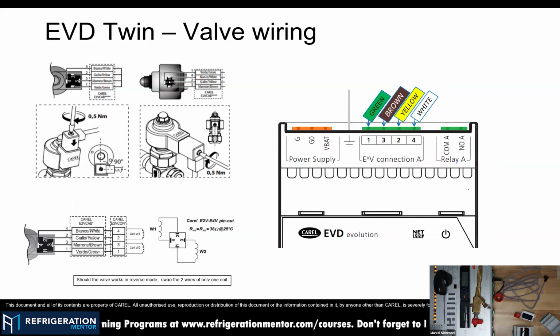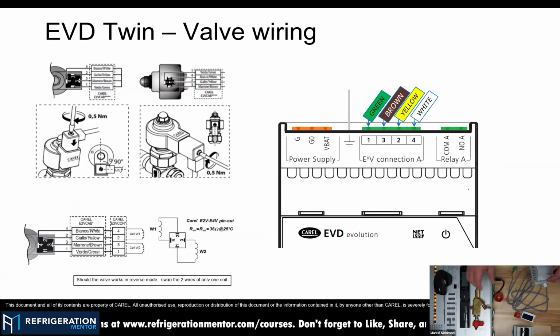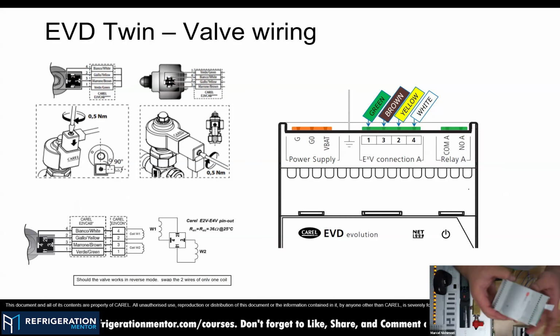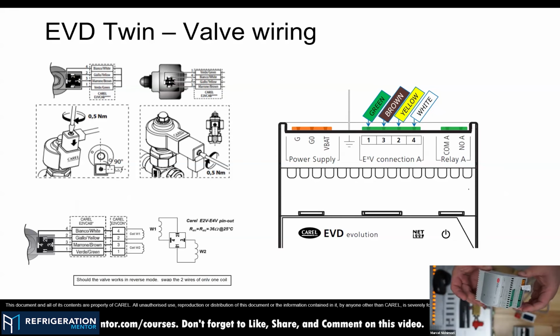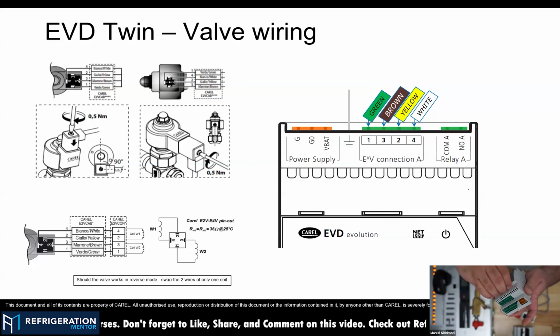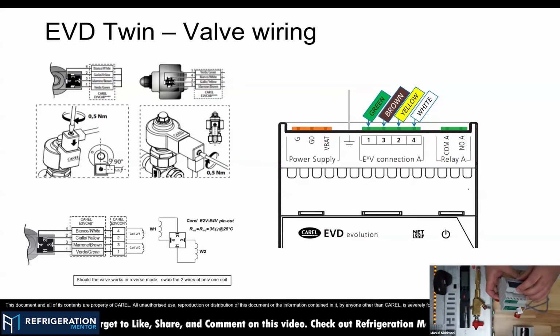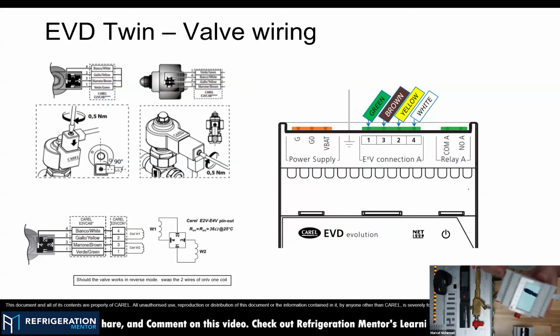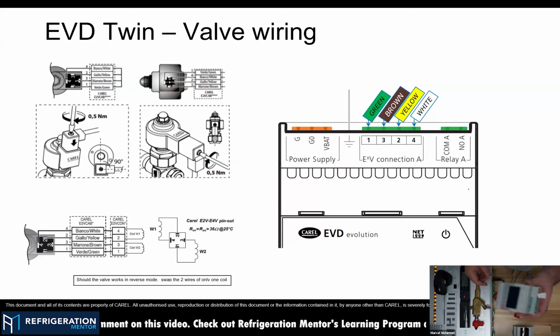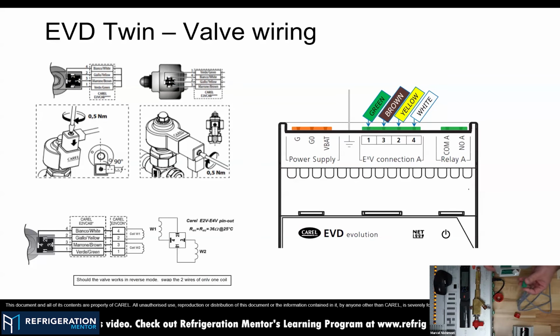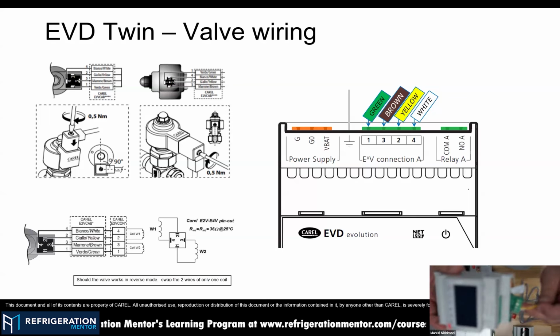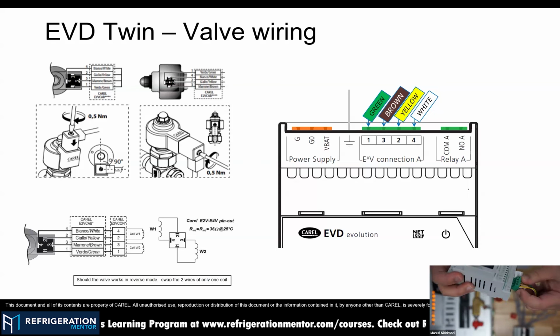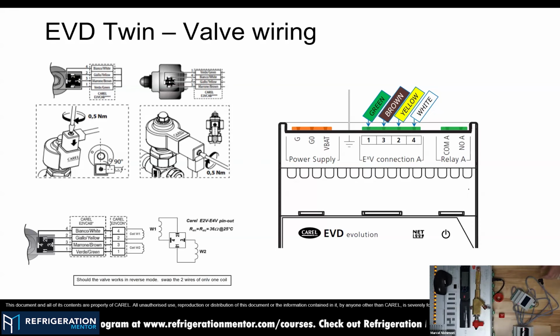Okay. And from the driver installation, what will drive the ejector? What are the controllers? I have here what we call the EVD driver. This is a driver for bipolar motors. We can use this for CAREL or third-party valves, and it has its own display. This device can be used for superheat control, but in this case, we are using it for driving the ejectors. You can see here that I put the colors because this is another common mistake on installation. So make sure that once you have wired it, it follows the right color sequence as indicated here. One positive thing is that when you are programming the EVD, the last screen of the initial programming is the sequence of colors that you need to use with the wires.